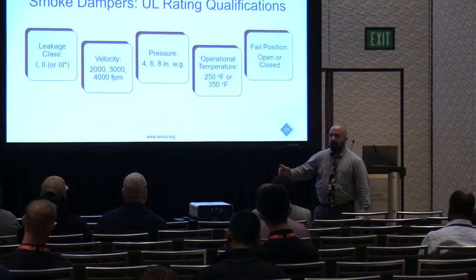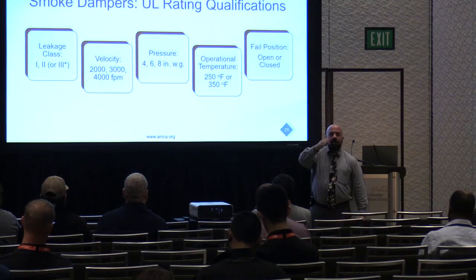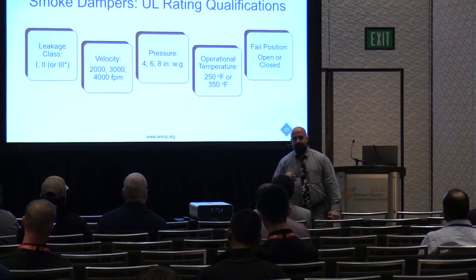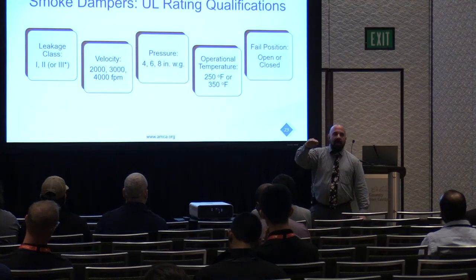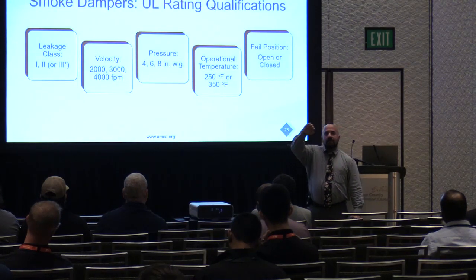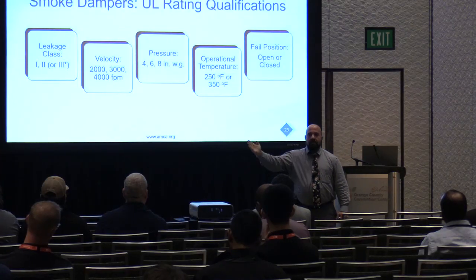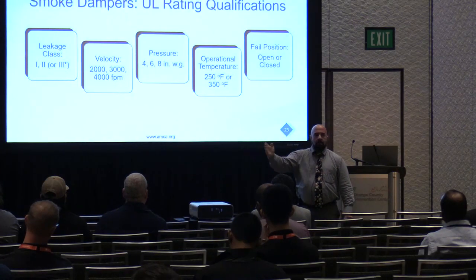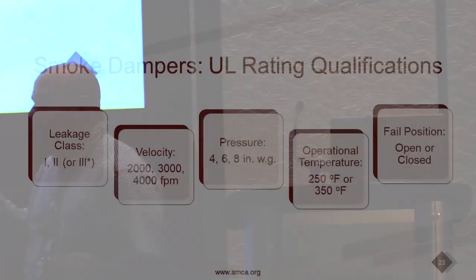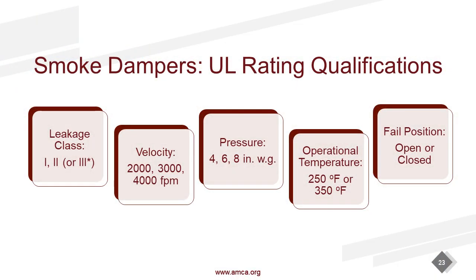that fire. But with smoke dampers, if that ductwork is part of your smoke control system, and your building loses power, and that damper fails in the closed position, that ductwork is effectively no longer usable. So you may need that damper to fail in the open position so you can continue to evacuate smoke and do what you need to do. This information should be detailed on your smoke control drawings, your control plan, or on your mechanical plans.